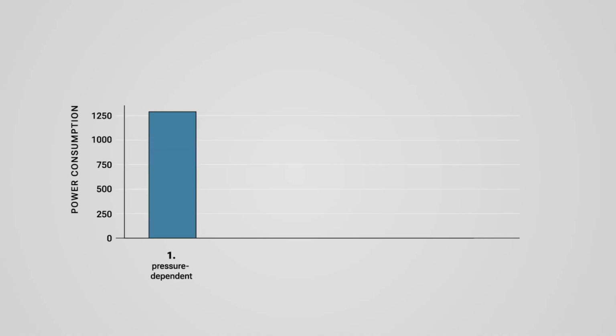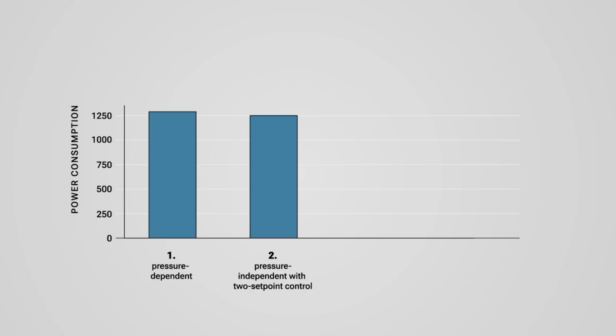Replacing pressure-dependent with pressure-independent valves with 2 set-point control brings a reduction of energy consumption for the pumps of 1% for cooling and 5% for heating.